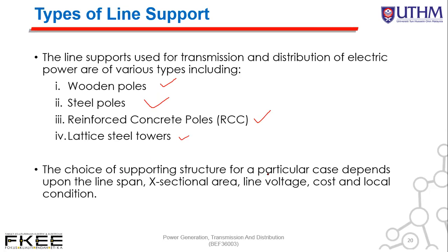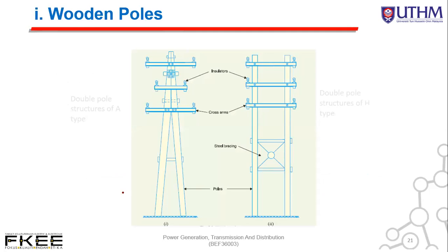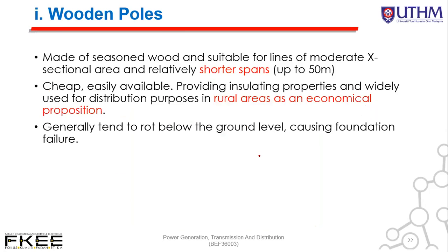The choice of supporting structure for a particular case depends upon the line span, cross-sectional area, line voltage, cost, and the local conditions. Now we look at the case of the wooden pole. Basically the whole pole structure is made of wood, and we can see the comparison between the double pole structure of A type and the double pole structure of H type. The wooden pole is made of seasoned wood and suitable for lines of moderate cross-sectional area and relatively shorter spans up to 50 meters. It is cheap, easily available, provides insulating properties, and is widely used for distribution purposes in rural areas as an economical proposition.